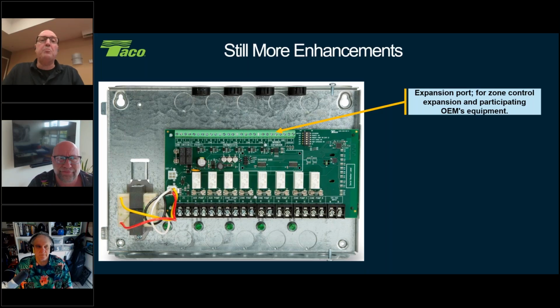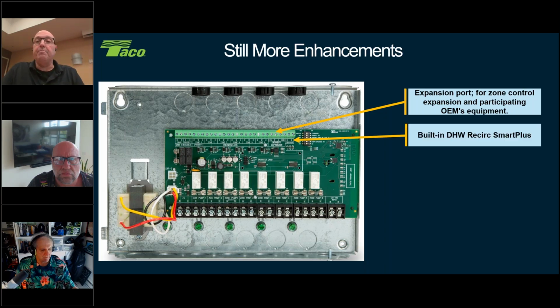We still have that same expansion port, which means you can daisy chain the boards from one to the other. Now, if you look at the board, you'll also see the word Modbus on there. That does not mean we have Modbus points in communication, but we do have some communication with OEM equipment, meaning some manufacturers can provide their points, and we can create some custom code to work back and forth with each other at the moment. Right now we don't have anything out there, but it's for future proofing this device, so we don't have to have a new control. It's something we can add in there.